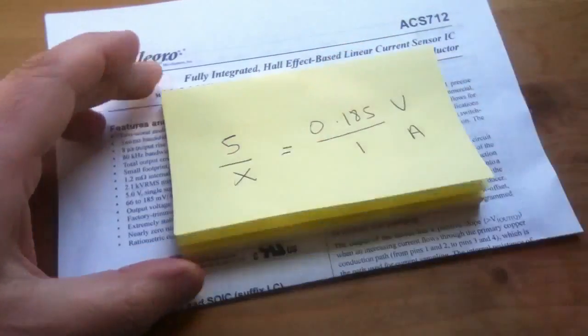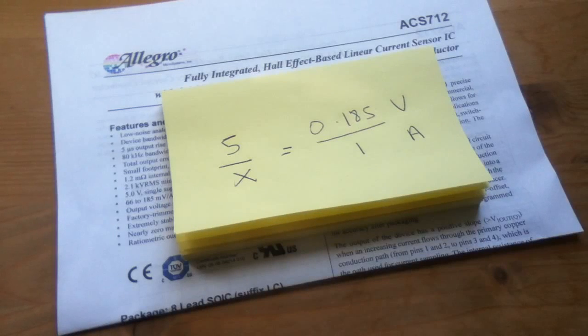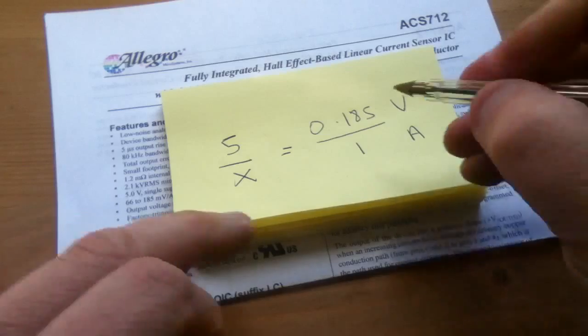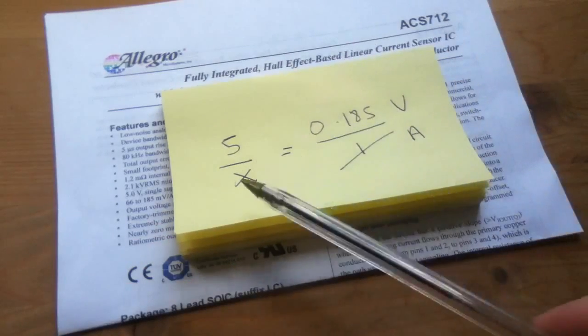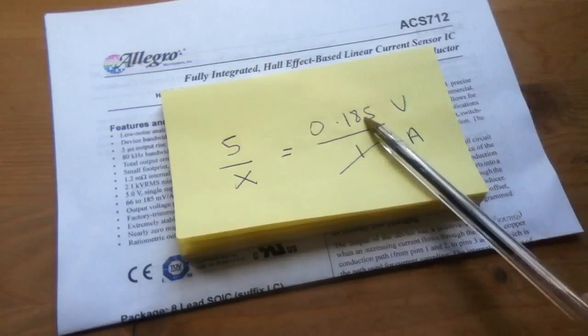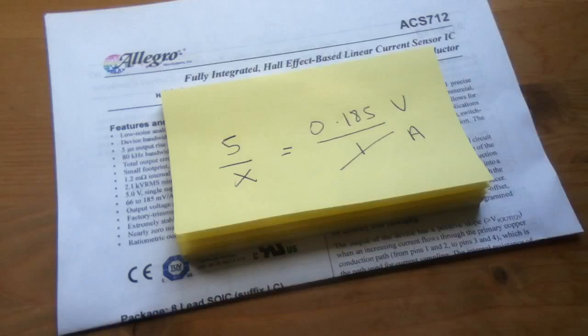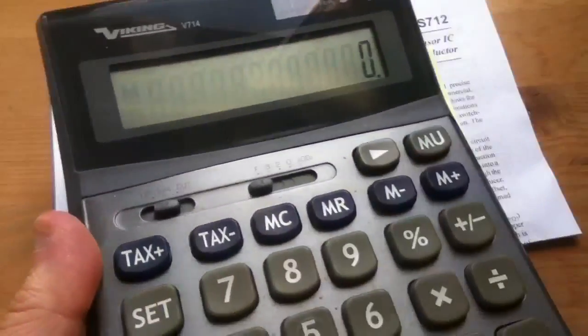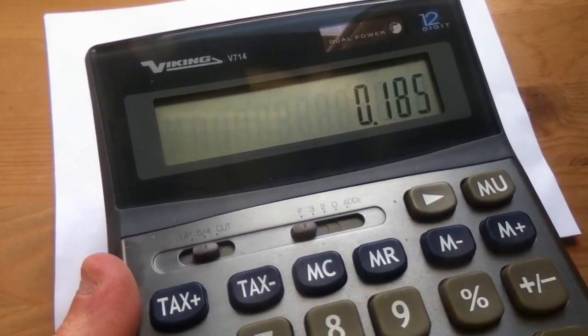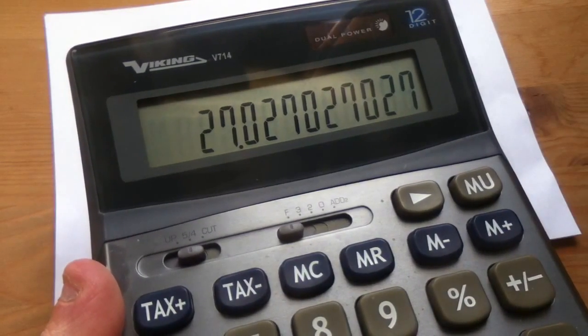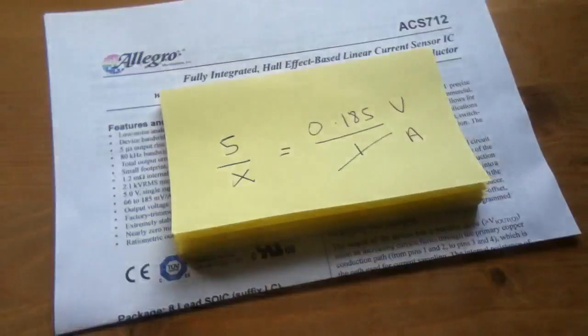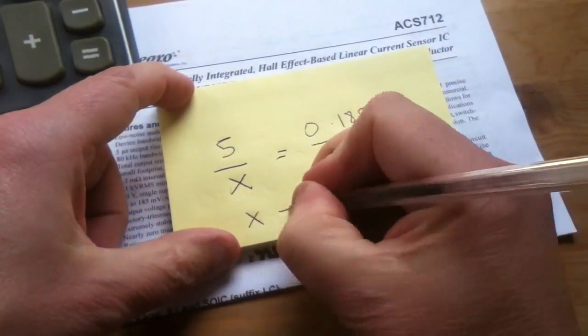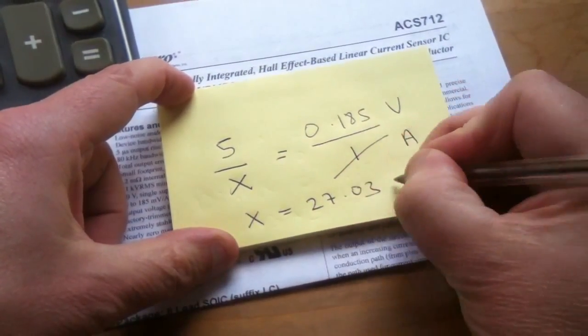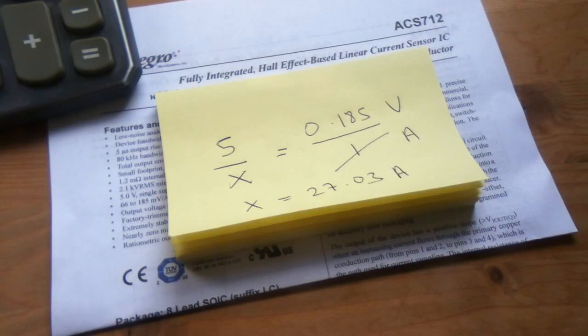So let's equate that to 5 volts, and our unknown there is x, and we have an algebraic equation. So what I can do is get rid of the 1, that cancels out, and if I swap x and 0.185, then x will equal 5 divided by 0.185. So, 5 divided by 0.185 is 27.03. So, x equals 27.03 amps. 27.03 amps will give rise to the full 5 volt swing on the output of this sensor.